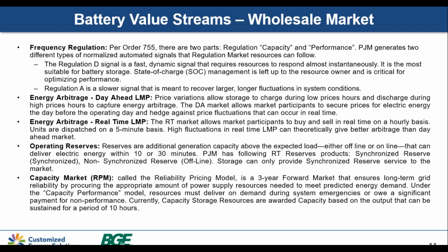Talking about operating reserves, this is a bit more storage-centric, because storage in PJM is considered synchronized to the grid due to its ability to respond instantaneously. Synchronized reserve is one of the more lucrative operating reserve products in PJM, which has different prices for synchronized versus non-synchronized reserve. Storage is always considered sync, so that's generally good. And due to the low number of synchronized reserve events in PJM, it's generally not going to degrade the battery much, because sync, as you can see, only requires you to deliver energy for a maximum of 30 minutes.